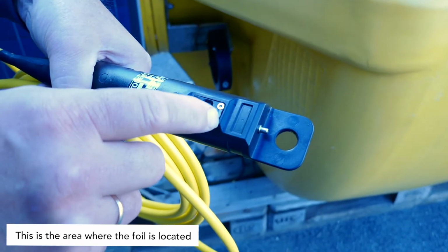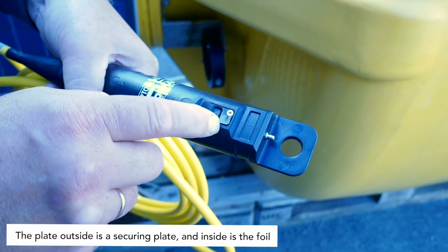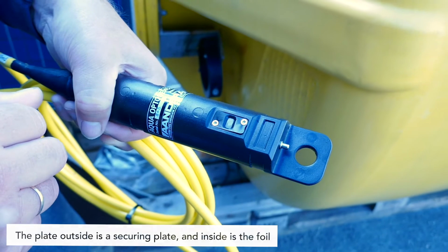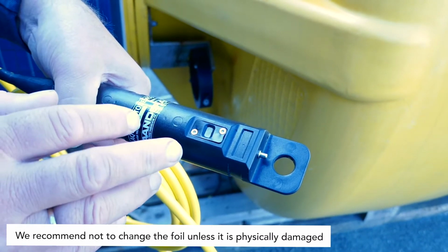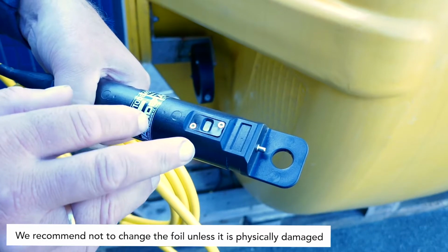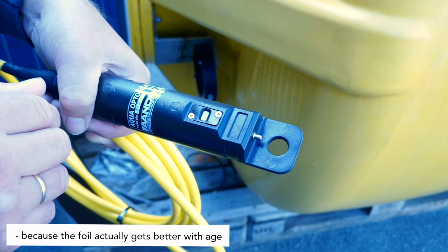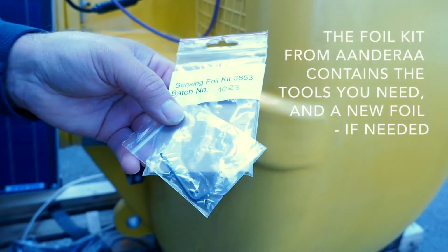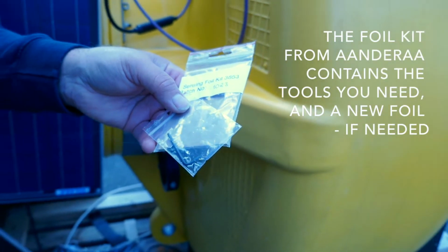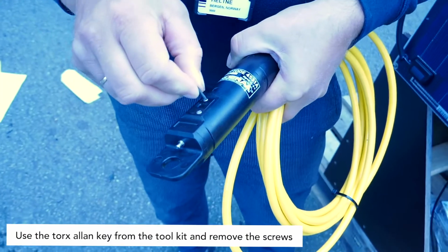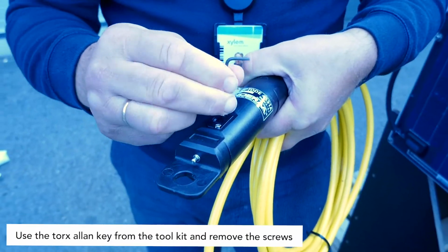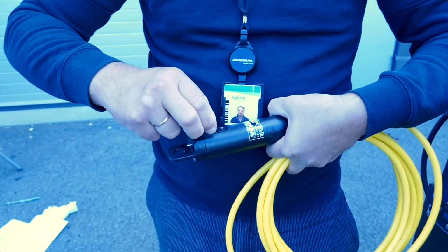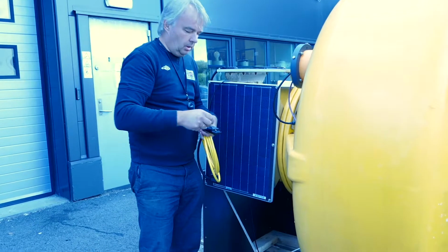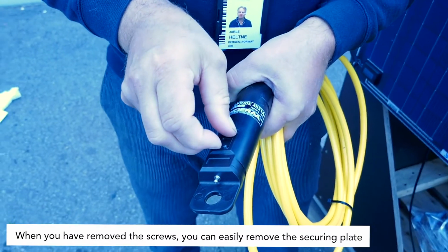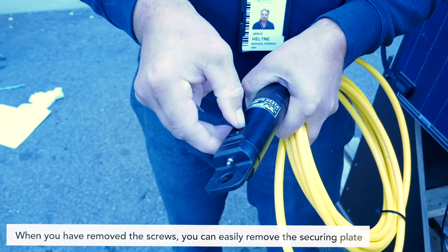This is the area where the foil is located, and this plate outside is just a securing plate, and inside there is the foil. We recommend not to change the foil unless it's physically damaged, because the foil gets only better and better the older it is. So after I remove the screw, I will easily be able to remove the securing plate, and behind there you will see the foil itself.